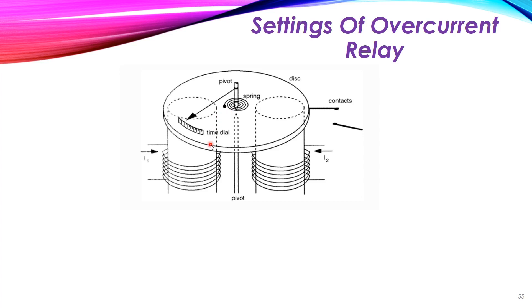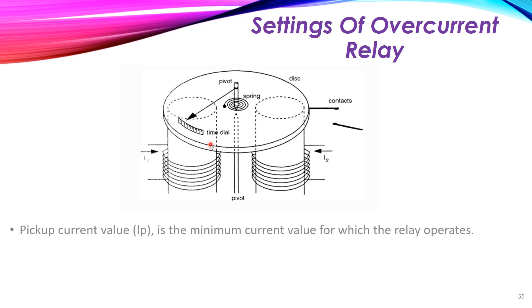To understand the settings of the overcurrent relay, we need to understand some definitions. The first is the pickup current, sometimes written as Ip. This is the minimum current required for the relay to operate — the current that produces a torque value exceeding the spring torque in order to rotate the disk.